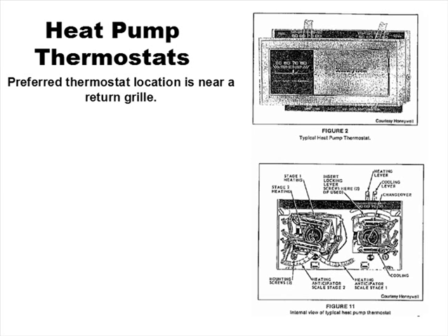Because it's lower pressure, it doesn't move at the speed of light, but it moves there usually at terminal velocity, about 25 feet per minute. When you get within 30 to 36 inches of that return grill, then you feel the effects of it. Take a candle, light it, get 3 feet away from the noisiest, fiercest, suckinest return grill you can find, and the flame in that candle is standing straight up.